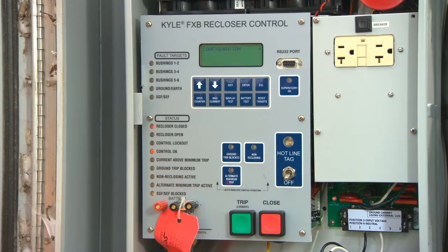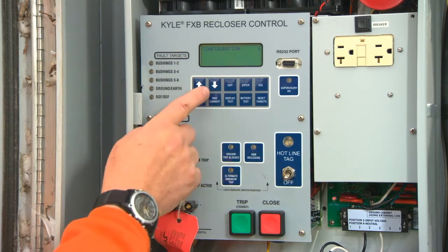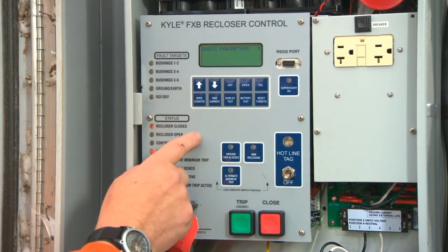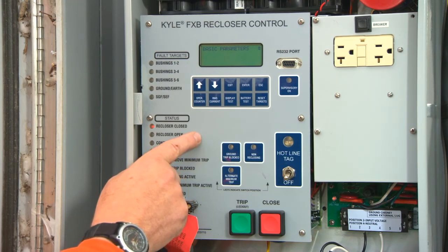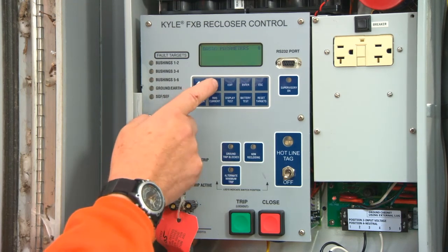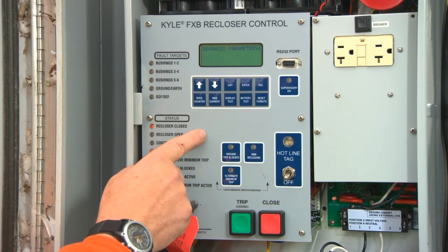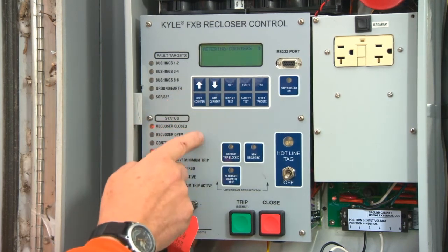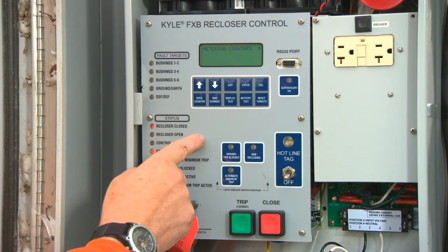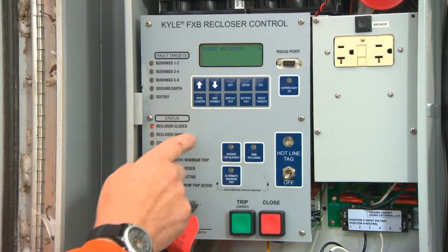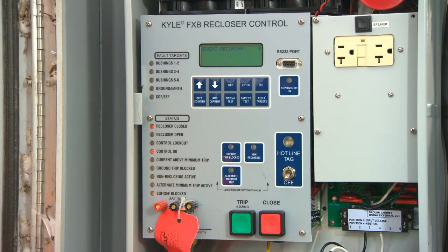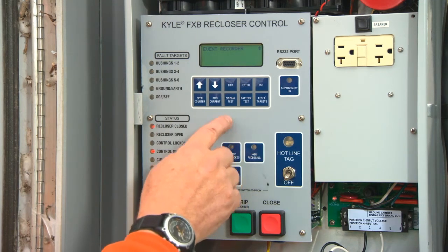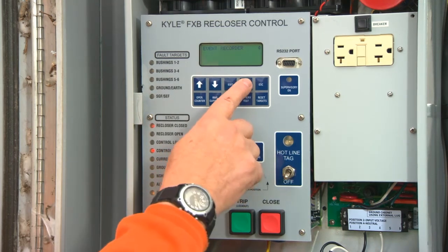From the configuration screen, use the arrow key to scroll down to Basic Settings. That will display the settings for this recloser. Scroll down again to view Advanced Parameters, Metering and Counters, and finally, Event Recorder, which is very useful to determine what caused the unit to trip. While on the Event Recorder screen, press the Enter button.